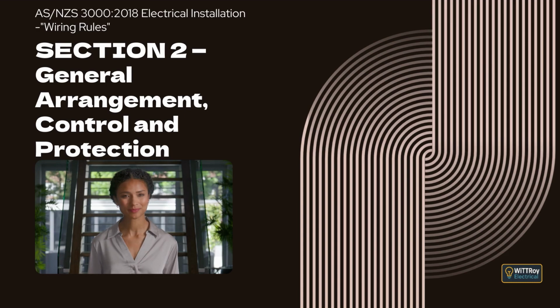The supply conductors feeding into the switchboard must also be arranged to reduce the chance of an arc starting. This can be done by using proper insulation or by separating conductors so that accidental contact is unlikely. The standard then explains that the switchboard must meet at least one of several approaches. The first option is to reduce the chance of an internal fault starting. The second option is to limit the harmful effects if a fault does occur. The third option is to use internal separation within the switchboard to prevent the fault spreading.